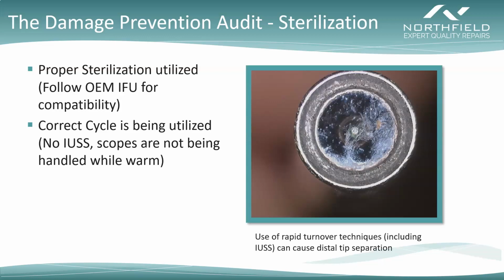And you'll begin to see stuff like this, where water spots are starting to accumulate inside of the scope, even though there may not be a huge amount of physical damage that's really obvious. What's happening here is the glass portion of the scope is beginning to pull away from the rigid stainless steel portion of the scope. And that's allowing water vapor to accumulate inside the scope, where hard water mineralization is beginning to build up, and that creates a very foggy image.